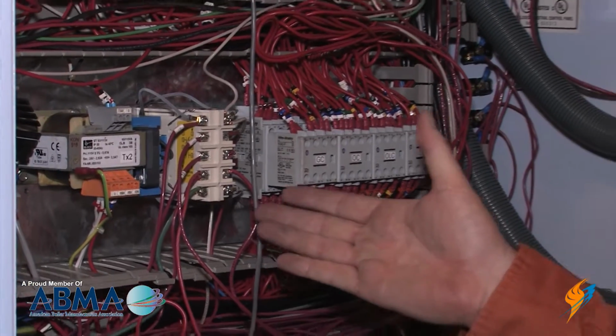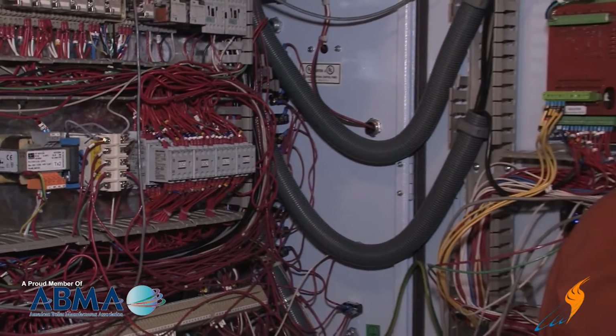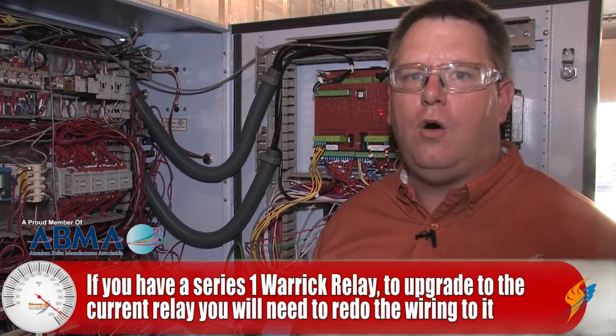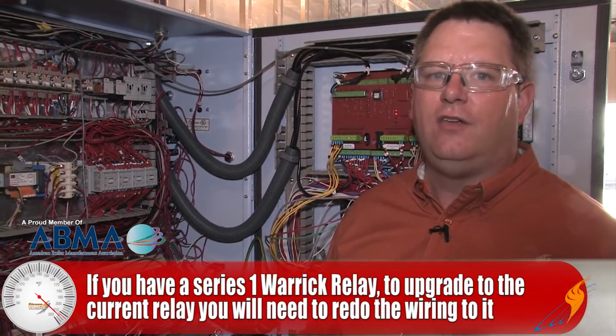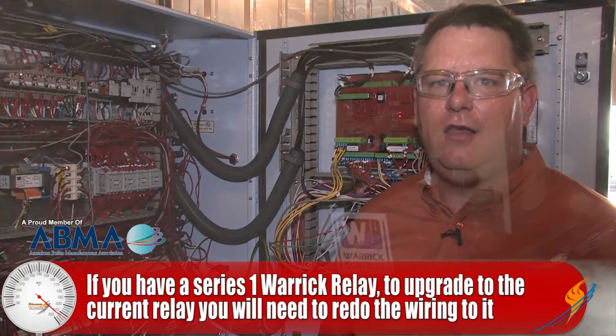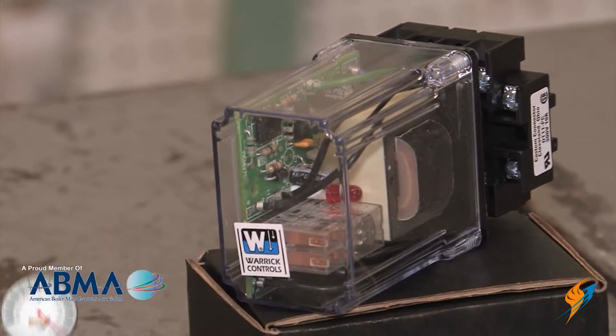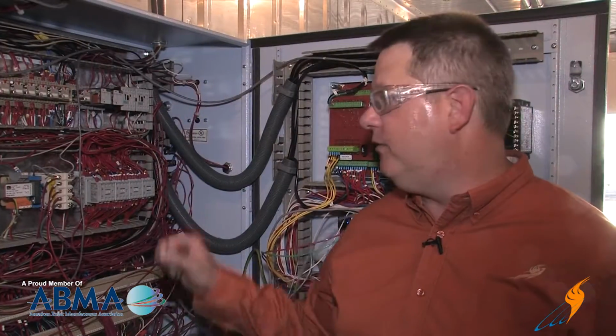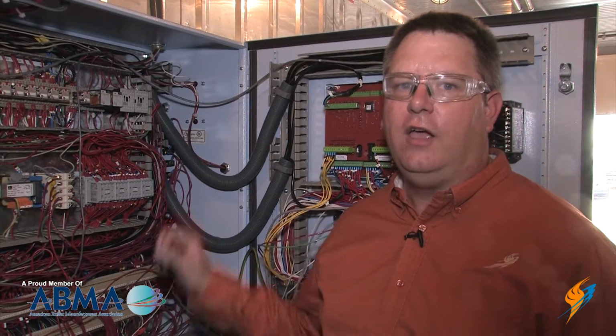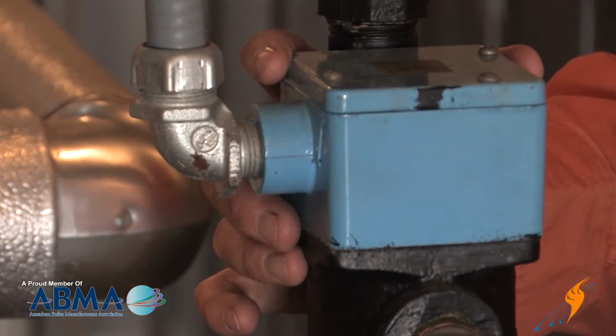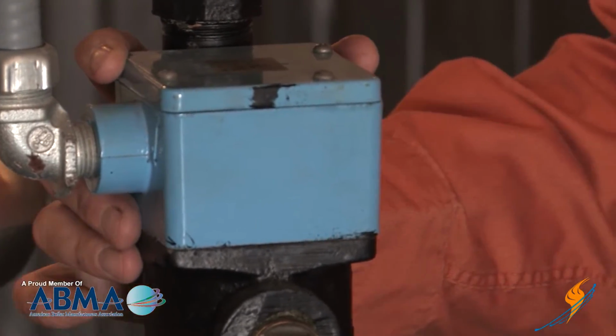This unit has a Series 1 Warrick low water cutoff relay. Those were phased out about 3 years ago, and the wiring on them is significantly different than the modern style or the replacement, and so it's critically important to understand that if you're going to change out an older style relay. One advantage of the probe type low water cutoff devices is this externally mounted pot.